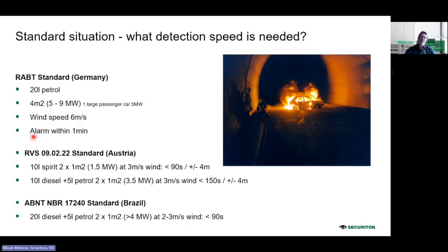Then if we compare it to the Austrian norm, they use quite a lot less diesel or spirit. And you see also here we have less energy during this fire test. It's going down to 1.5 or 2 megawatts. But on the other side, they use less wind speed and give a little bit more time to detect an alarm, up to 90 seconds. This is because the fire is smaller, so we have less power, which means we need a little bit more time to detect this temperature increase inside the tunnel. They do different tests. They do also diesel mixed with petrol, so here we increase up to 3.5 megawatts. And also here we have 3 meters per second, where they also tolerate around 150 seconds to trigger an alarm.